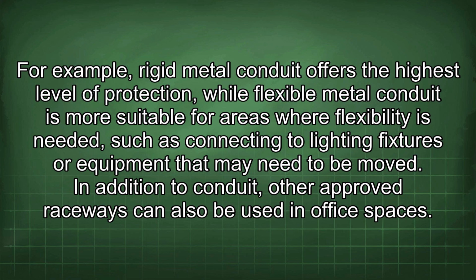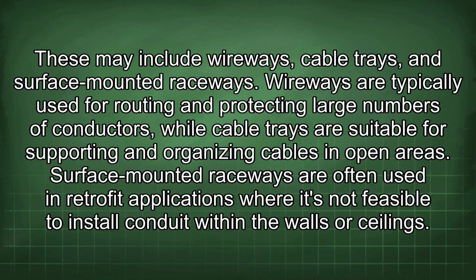In addition to conduit, other approved raceways can also be used in office spaces. These may include wireways, cable trays, and surface-mounted raceways. Wireways are typically used for routing and protecting large numbers of conductors, while cable trays are suitable for supporting and organizing cables in open areas. Surface-mounted raceways are often used in retrofit applications where it's not feasible to install conduit within the walls or ceilings.